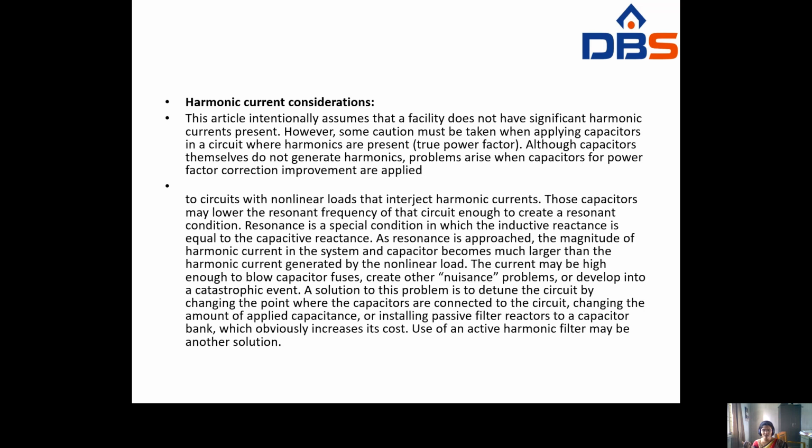So what is resonance? Whenever the inductive reactance is equal to the capacitive reactance, that is resonance. As resonance is approached, the magnitude of the harmonic current in the system and the capacitor becomes much larger than the harmonic current generated by the non-linear load.